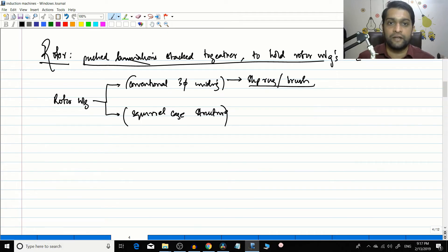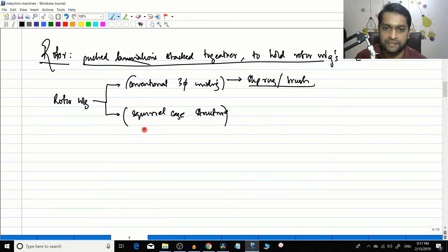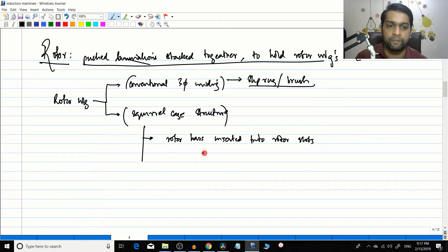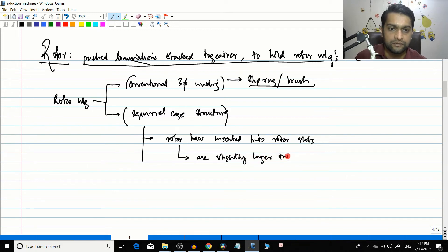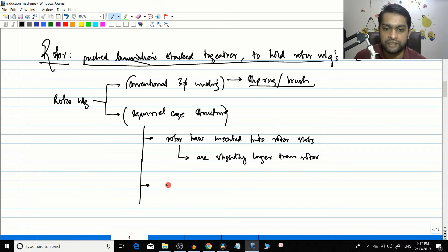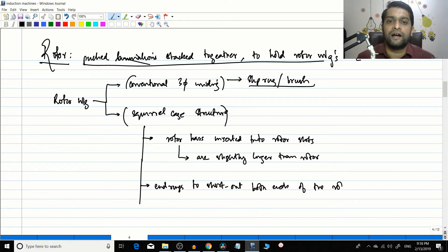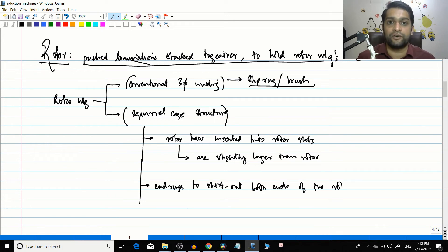The squirrel cage structure consists of solid rotor bars inserted into rotor slots. These rotor bars are slightly longer than the rotor itself, and end rings are used to short out both ends of the rotor. Shorting is necessary because once the induction process happens, current must circulate — if both ends are open, current cannot flow.